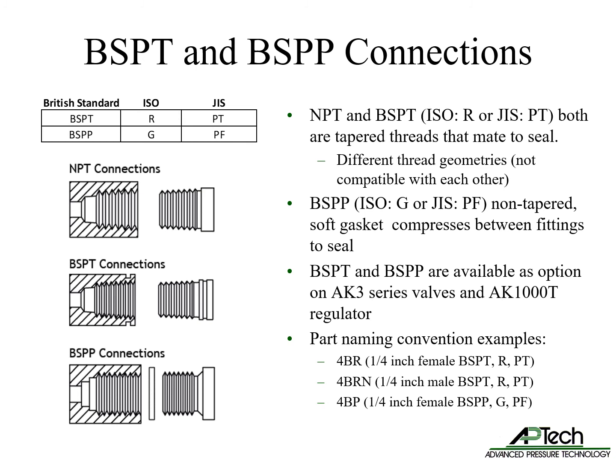BSPT and BSPP connections are also available on select products. The tapered BSPT connection is also called R in ISO and PT in JIS naming conventions. BSPT is similar in function to an NPT connection, but the thread geometries are not compatible. BSPP is non-tapered and uses a soft gasket compressed between a male and female fitting to seal. These connections are available as standard options on AK-3 series valves and the AK-1000T regulator. Examples of the naming convention include 4BR or 4BRN for 1/4 inch female and male BSPT connection respectively, and 4BP for a 1/4 inch female BSPP connection.